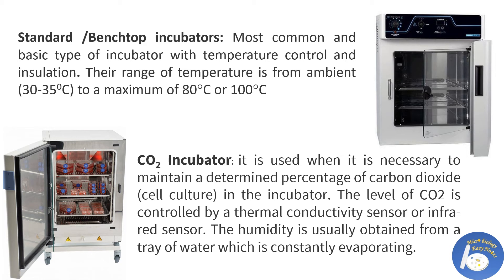The CO2 incubator is used when it is necessary to maintain a determined percentage of carbon dioxide inside the incubator, such as during cell culture incubation. The level of CO2 is controlled by a thermal conductivity sensor or infrared sensor. To control humidity, a water tray is present in the incubator.